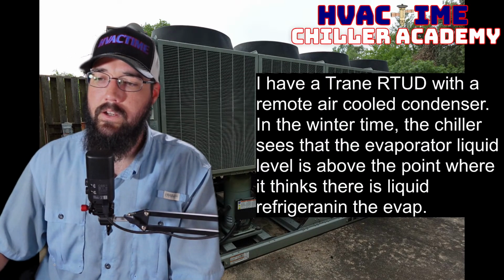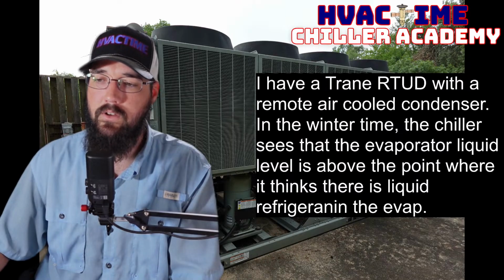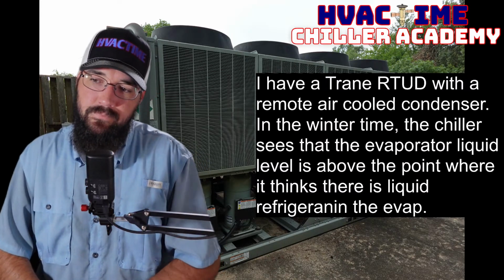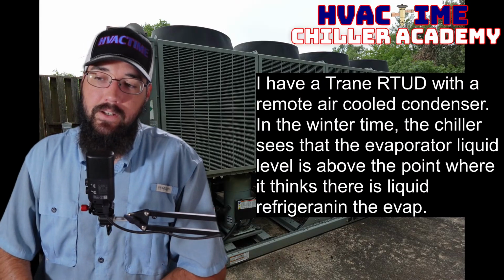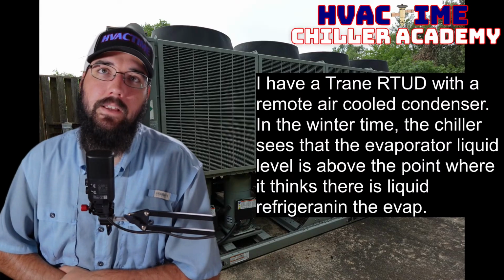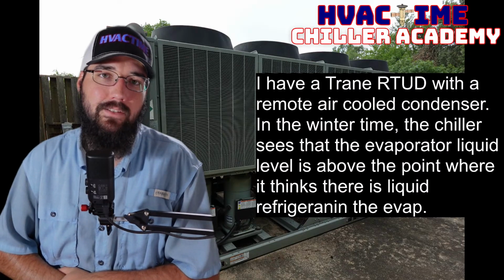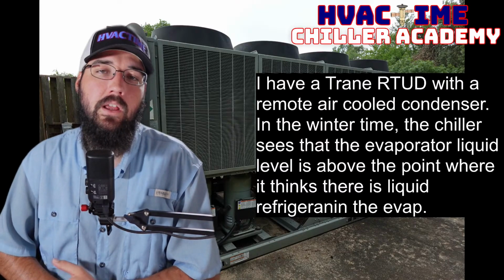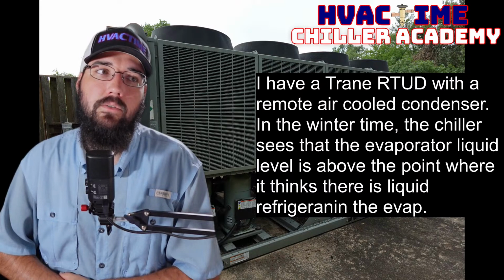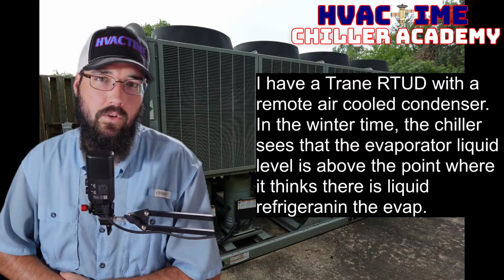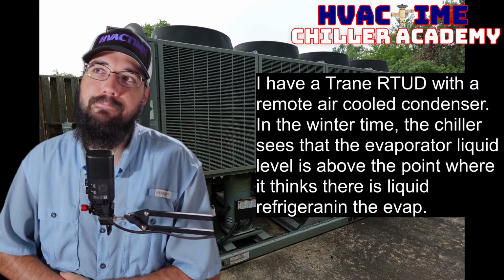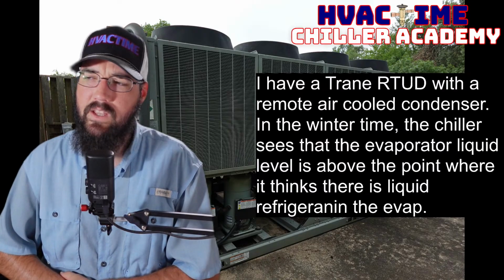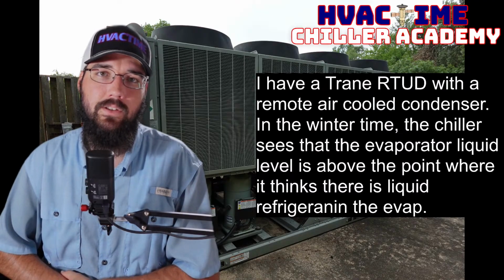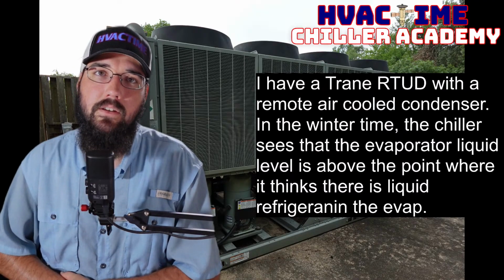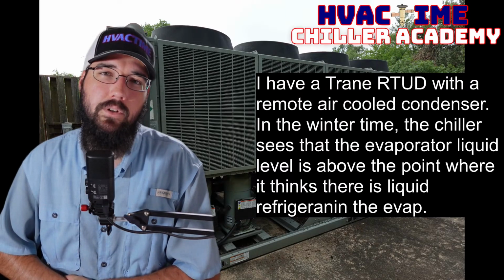So the BMS short cycling the chiller could contribute to this because the BMS often shuts down the chiller when it's running full out. Short cycling, yes. If it is, because that oil return system needs time and operating time in order to function. And so if we're giving that chiller short spurts of run, and I mean we're talking less than an hour. If it's having to do a startup and it's getting an hour or less of runtime and then shutting back down, then you do that often enough, yeah, you probably would have more migration issues.